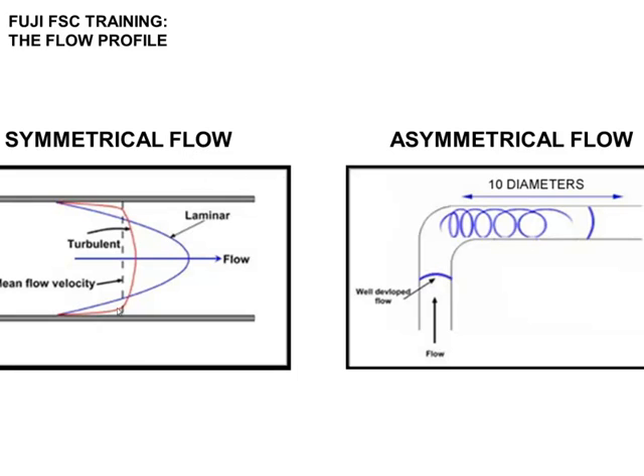If we were to cut away the pipe wall and look inside the pipe, these elliptical shapes represent the flow, either laminar or turbulent, or fast or low flow rate. What is important about them is the flow rate is the fastest at the center in both of these. Analogy, a man in the motorboat going down a river with the weight cast out to the side. In this case, the liquid's going through the pipe, and then either gravity or friction is grabbing a hold of the process liquid and making it go a little bit slower here than it is here.